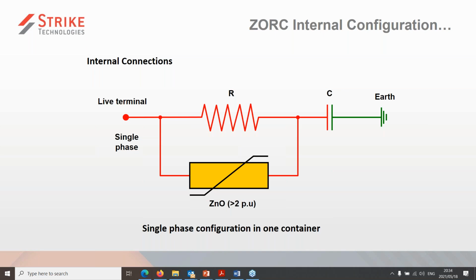Then by default, inserting those components into the system and allowing those resistive elements to perform their function. The capacitive element is also pretty much optimized to minimize heat dissipation and the stressing of the resistive elements under those fundamental frequency conditions. Also, simultaneously acting as a frequency dependent switch and as a wave sloping capacitor. So the waves that we saw in the previous graph had significantly sloped. We did not see that steep wavefront effect of the transient without protection. And then the function of the capacitor is to assist in sloping that wave under the high frequency transient conditions.